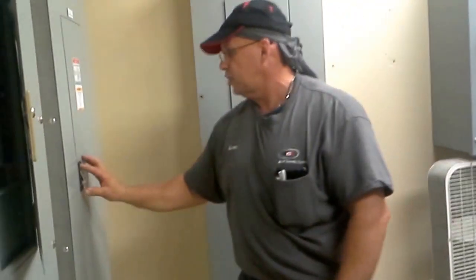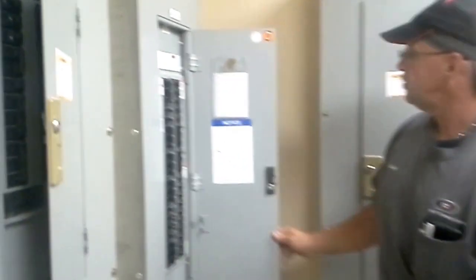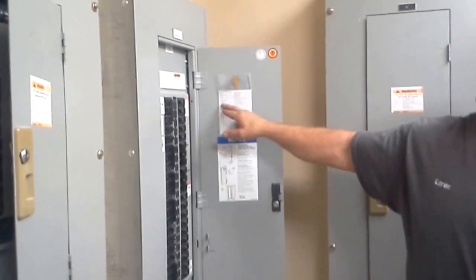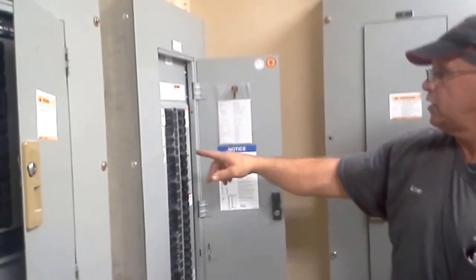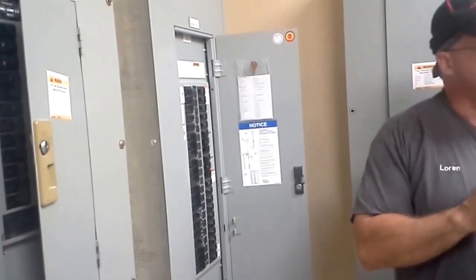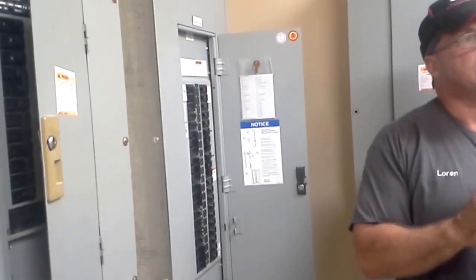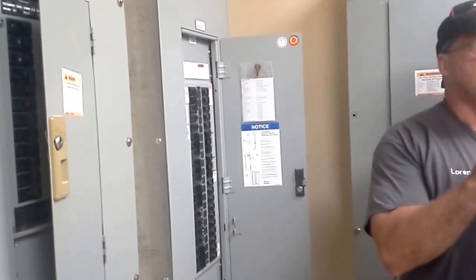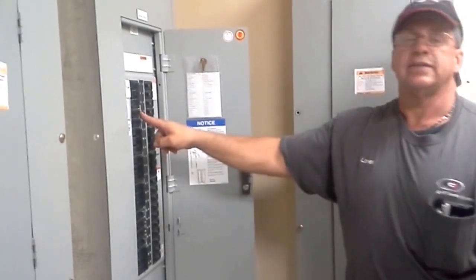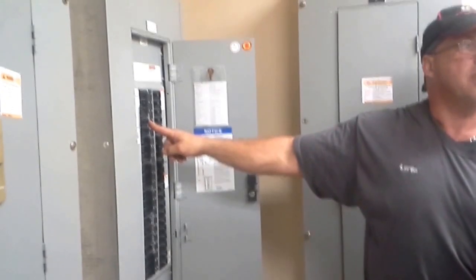Quick one here that I didn't think of. In this panel right here are your 120-volt receptacles, battery charger, and this one is called your jacket heater. That's your coolant heater, number 7 and number 9. If anybody ever goes over there and changes that start battery, which is recommended every 2 years, if they ever have to replace that, by God, turn this off. Turn that battery charger off.